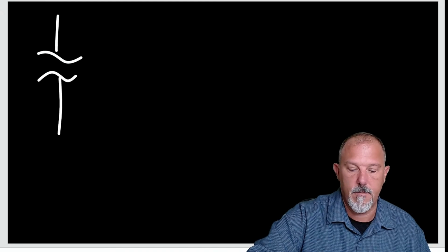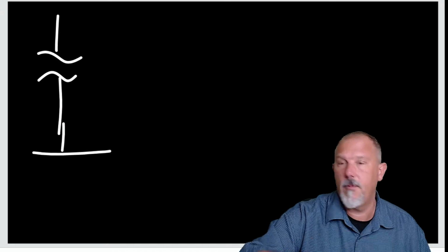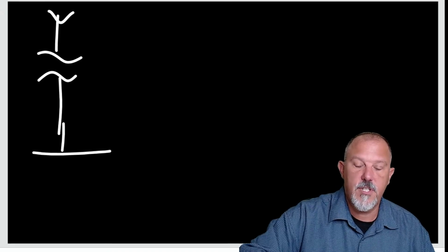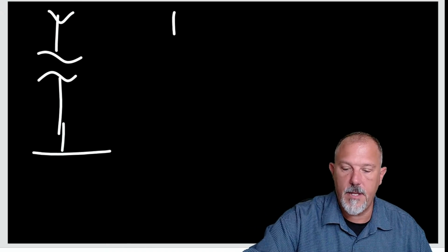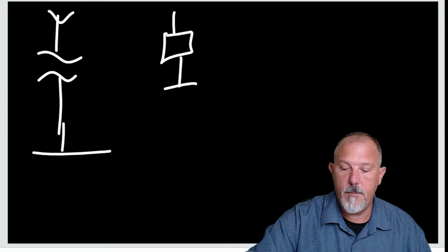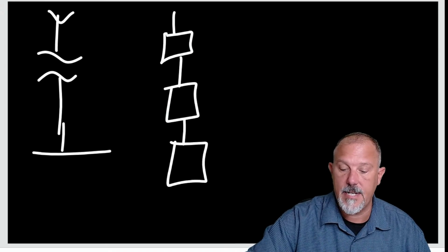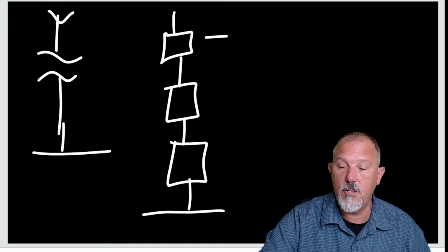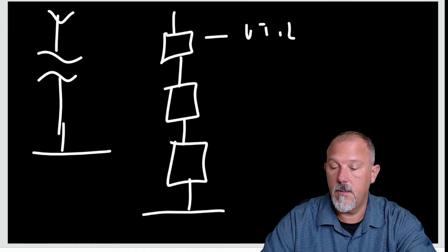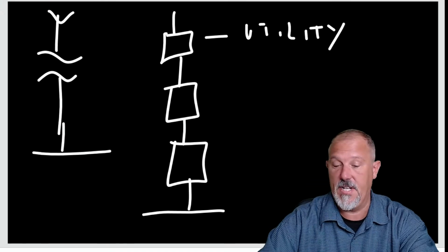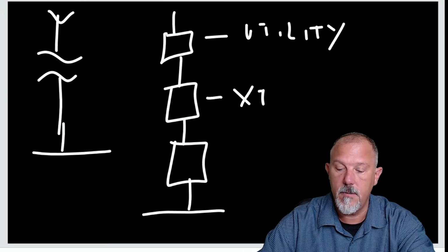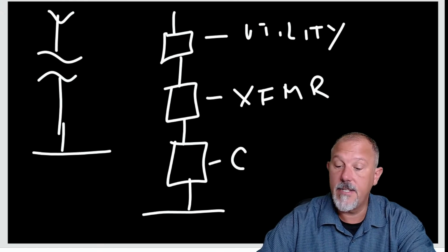Delete. Okay, so what I'm going to do now is, we were talking about the impedance diagram. So if I have a transformer, and it looks something like this, right? And let's say that it's feeding a panel, and I'm not going to draw the circuit breaker. And there's a utility up above. How I would model this is an impedance for the utility, an impedance for the transformer, an impedance for the secondary conductor. Okay, so this is the utility. Oh man, I don't have my pen, so I'm using my big fat finger. That's my utility. This is my transformer. And this is my conductor.